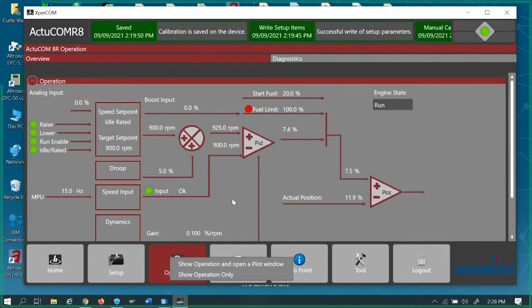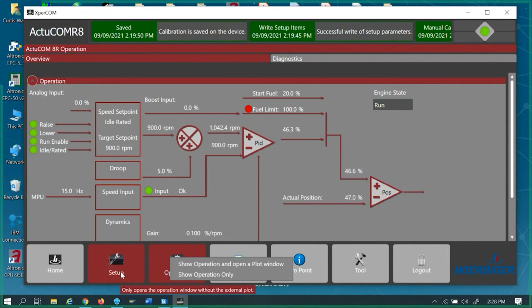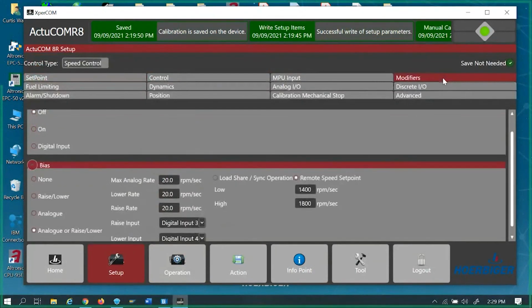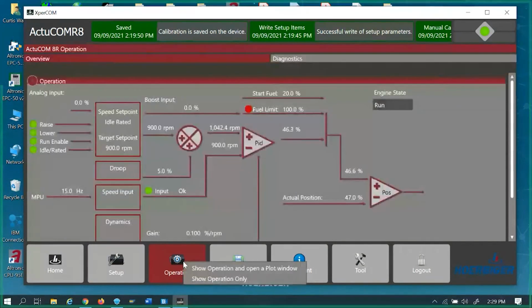All right. So remember we had the modifiers here for a 4 to 20. So right now my modifiers were set at a minimum 1400 to 1800. I'll go back to my operation page and we'll look. This should be going to 1400 because I'm at basically 4 milliamps. I took that low milliamp and high milliamp shutdown off, basically that deal. So here I am at 1400.